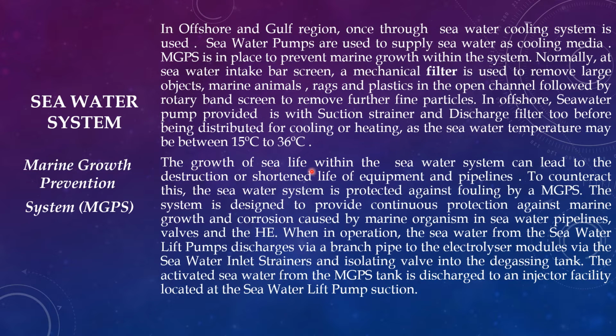The growth of sea life within the seawater system can lead to the destruction or shortened life of equipment and pipelines. To counteract this, the seawater system is protected against fouling by a marine growth prevention system. The system is designed to provide continuous protection against marine growth and corrosion caused by marine organisms in seawater pipelines, valves, and the heat exchanger. Also, due to the salinity of the seawater, it will cause more corrosion to the seawater line.